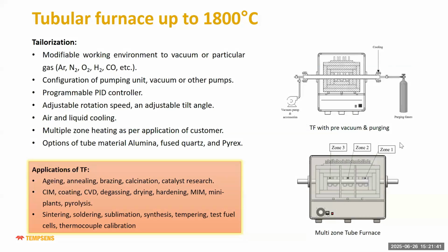Then the same thing is also applicable for the 1800 tubular furnace, where we can do customization, like different atmospheres we can provide, vacuum pump we can provide, programmable PID controller, adjustable rotation speed, air and liquid cooling, multiple zones. Like if you need better uniformity, we can give you multiple zones for the controlling. Different types of tubes we can provide as per the requirement. And applications of tubular furnace can be aging, annealing, brazing, calcination, catalysis, CIM, CVD, degassing, drying, hardening, MIM, sintering, soldering, sublimation, like that.